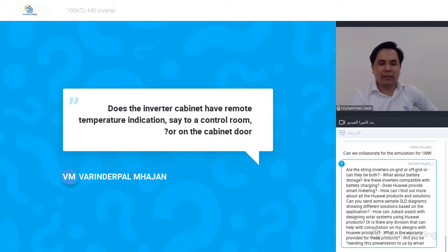Does the inverter cabinet have remote temperature indication, say to a control room or on the cabinet door? On Fusion Solar, you can monitor the internal cabinet temperature, and if you want to access the data in a control room, you can do Modbus interfacing and get this data from the Huawei Smart Logger. Since there is no LCD screen on the Huawei inverter, there are only LEDs. Therefore, you cannot see such information on the inverter itself.